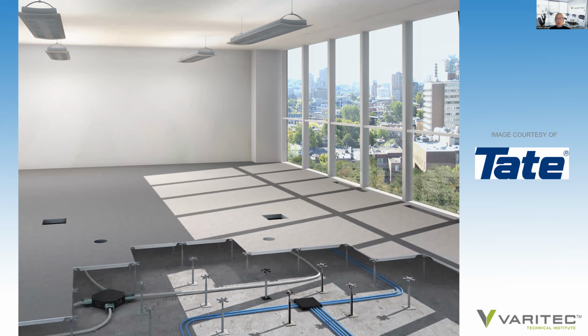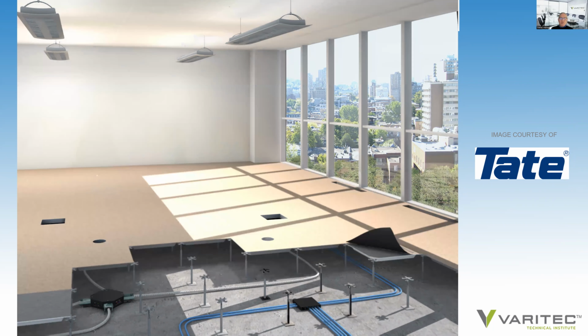Each of the tiles are pre-cut by the floor manufacturer, and consequently, when it comes for the mechanical contractor to install the diffusers, they just bring the diffusers to the hole, pop them in, and secure them firmly to the panel. Be aware, you want to make sure you have a manufacturer that has a securing capability of the devices to the floor panels. Not all of them do, and it would need to be addressed if you're considering looking at and designing to an underfloor air system.